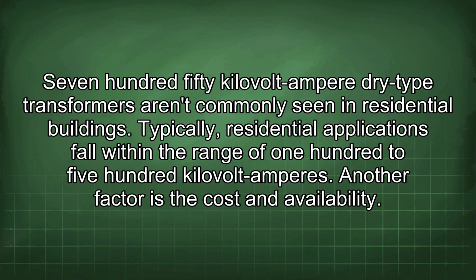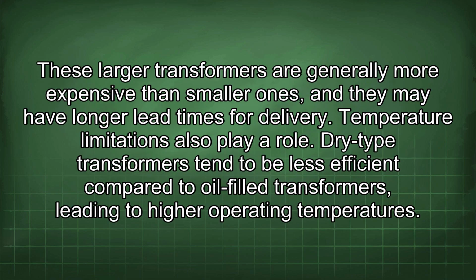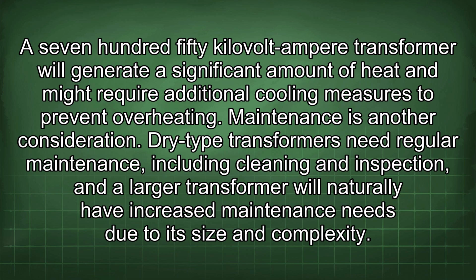Another factor is the cost and availability. These larger transformers are generally more expensive than smaller ones, and they may have longer lead times for delivery. Temperature limitations also play a role. Dry-type transformers tend to be less efficient compared to oil-filled transformers, leading to higher operating temperatures.